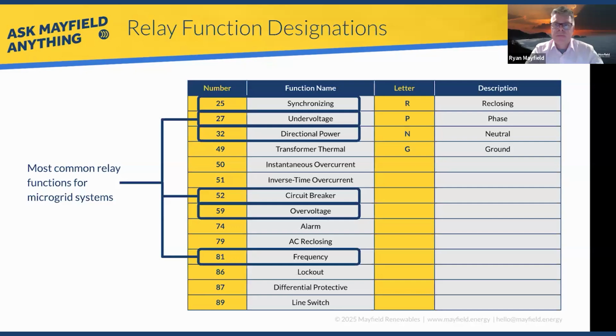I specifically mentioned the interconnecting elements in 1547, but that really protects the electric utility and its other customers. Looking at the elements listed here, I noticed 51 elements and 50 elements. As consultants and engineers, we also have to consider protecting the equipment we're interconnecting to the system, and that's where the 51 elements come in, or maybe even an 87, a differential device that protects the transformer we're connecting.